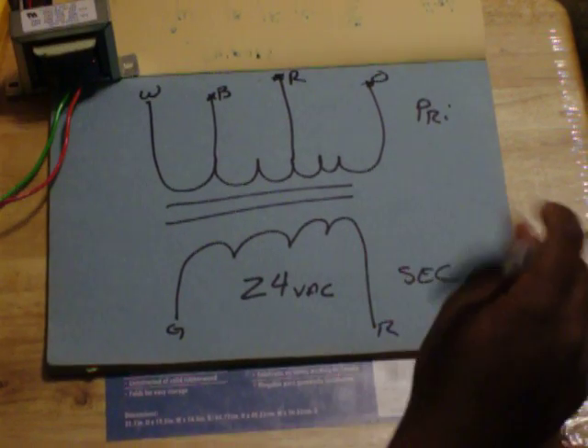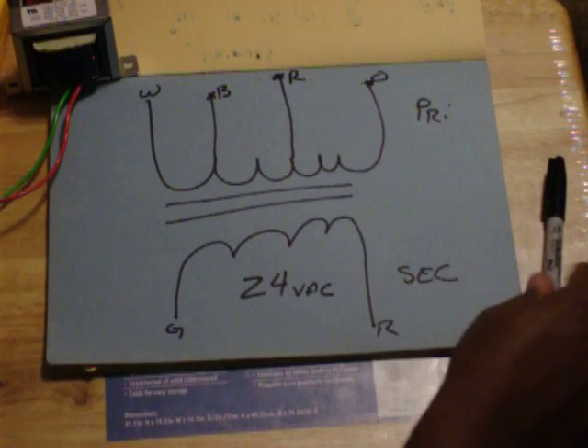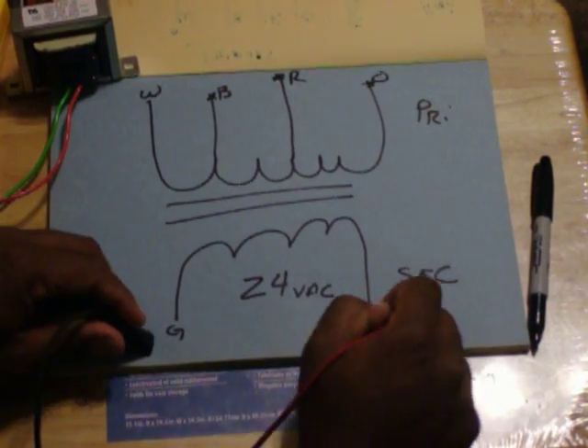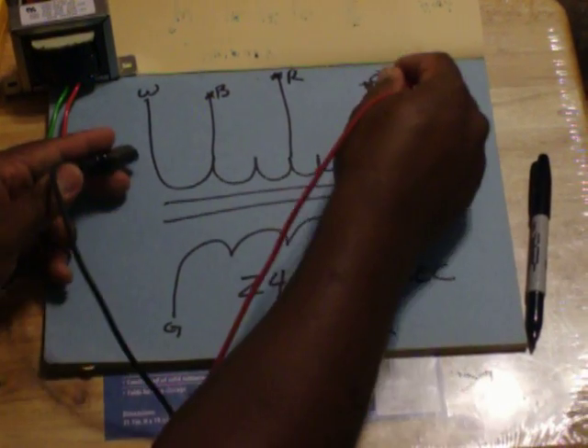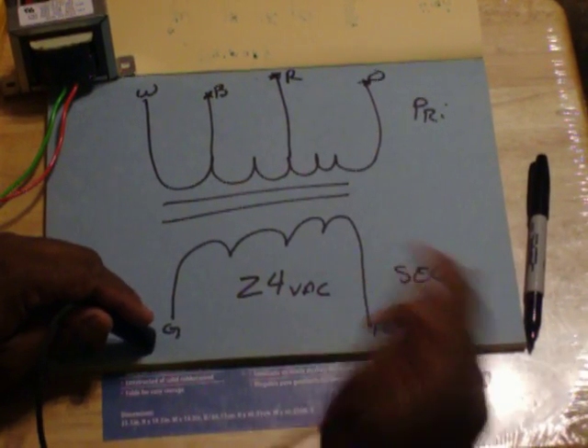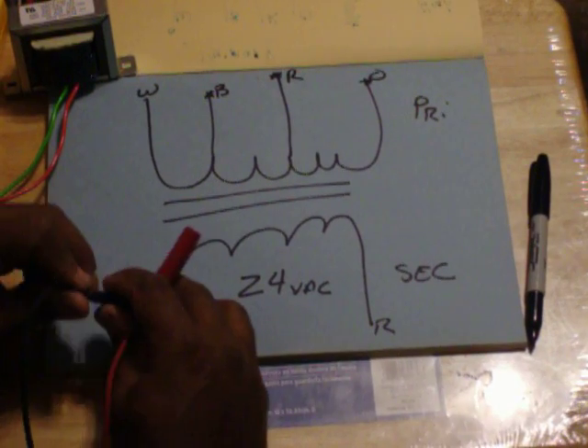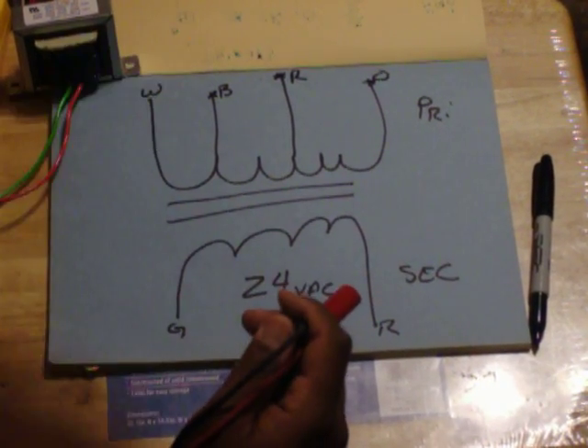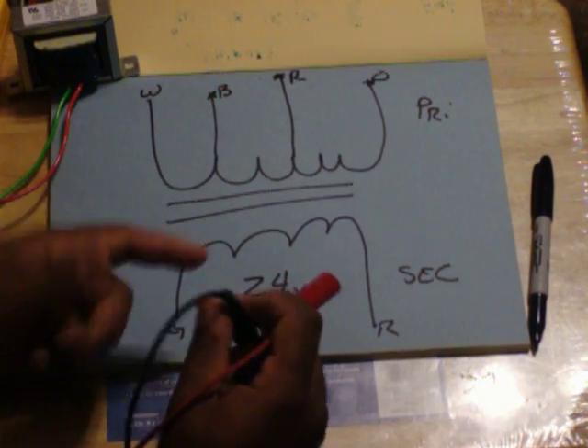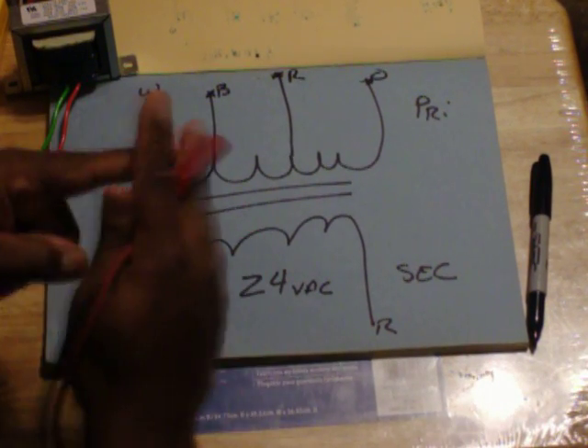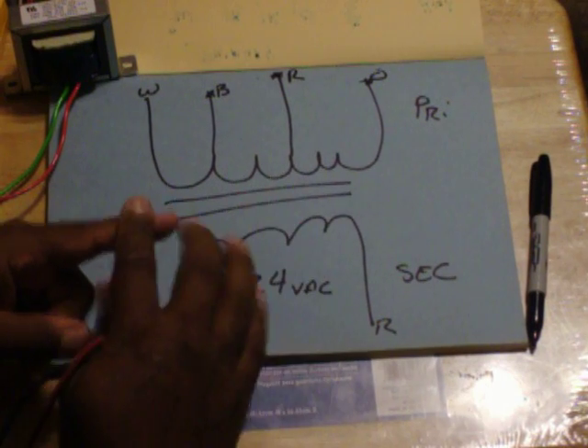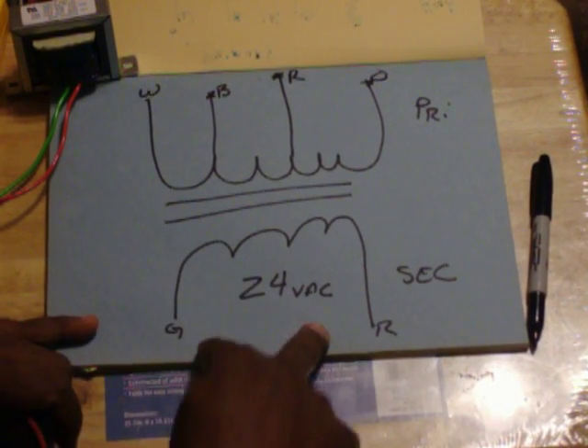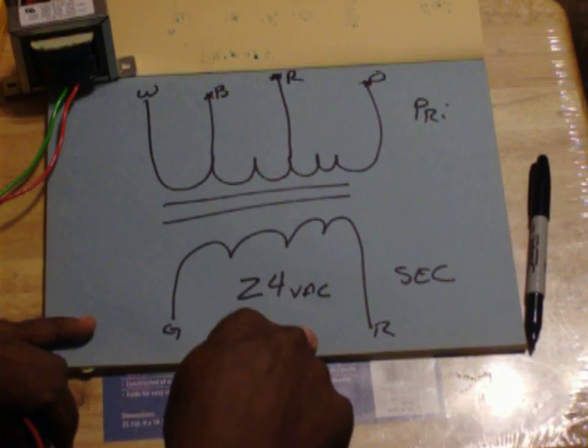Checking this is very easy. If you want to check it with power applied to it, you simply check power going in and power coming out of it. If you have power going in and you don't have power coming out of it, it's bad. It's important to know which side is burnt out. If it's your secondary side is burnt out, you have a load, a contactor, a relay. One of your wires could be rubbing together. I've seen them go to the condensing unit and rub together and short out. Something down here that this feeds is shorted out.